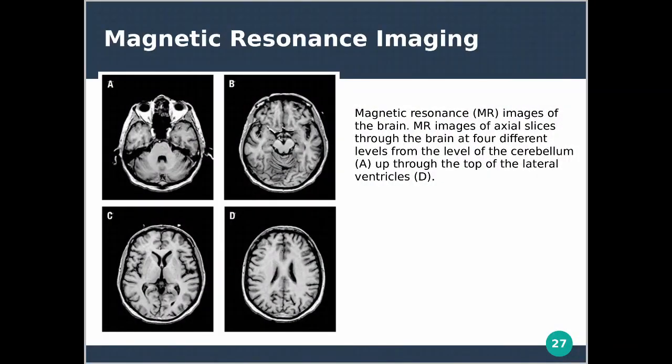Now, the downside here is that since it uses a large amount of magnets, the mechanism is a bit claustrophobic, of course. You cannot subject a person that has steel or metal, for example metallic legs, metallic implants or braces, to MRI. At least you need to remove those metallic implants first, because MRI produces strong magnetic fields, which your metallic implant is very susceptible to. So that's one of the downsides.